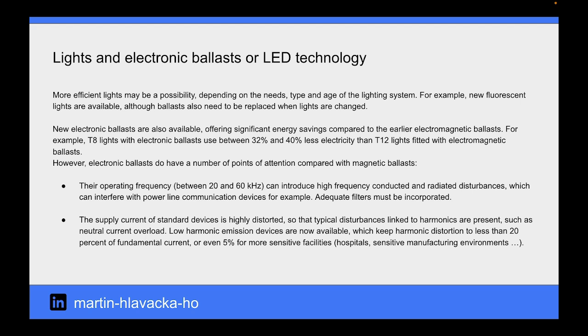Their operating frequency can introduce high frequency conducted and radiated disturbances which can interfere with power line communication devices. For example, adequate filters must be incorporated, and the supply current of standard devices is highly distorted, so that typical disturbances linked to harmonics are present, such as neutral current overload. Low harmonic emission devices are now available, which keep harmonic distortion to less than 20% of fundamental current, or even 5% for more sensitive facilities like hospitals.